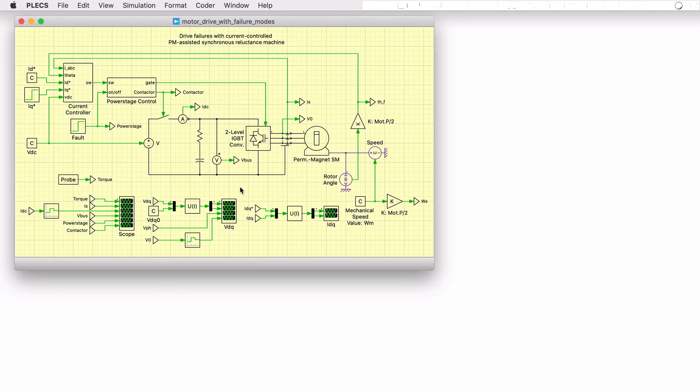This PLECS demo model examines a current controlled permanent magnet machine with drive fault mitigation strategies. When operating in flux weakening mode, a fault mitigation strategy may be required as the rectified back EMF may be larger than the DC link voltage.